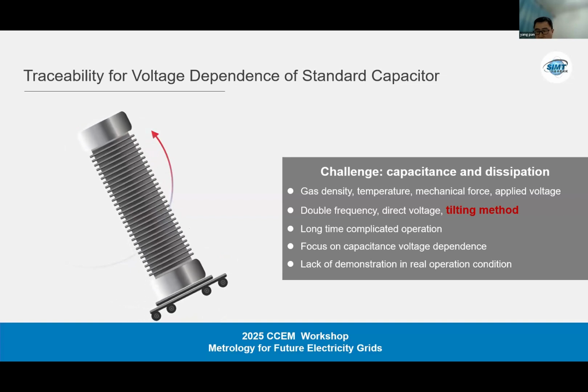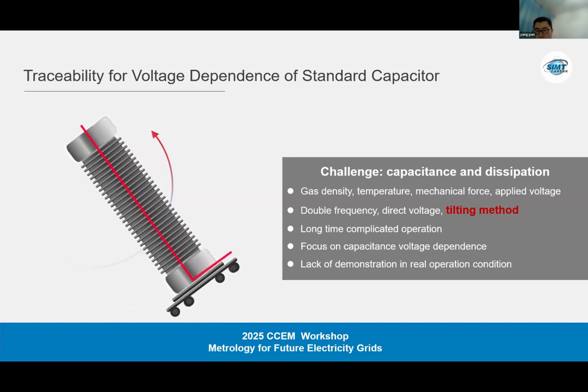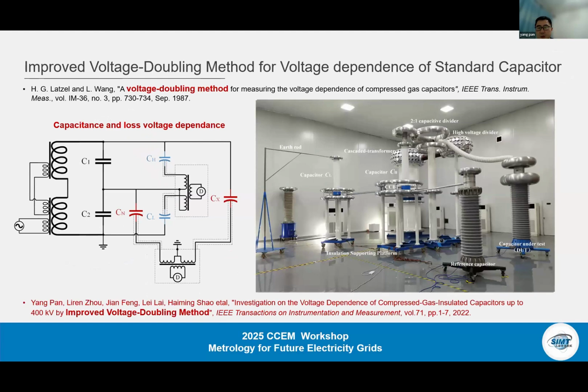Investigation has been carried out in this field, including the double frequency method, DC biasing method, tilting method, and also the voltage doubling method. Among all these test methods, the voltage doubling method offers a key advantage: the simultaneous determination of both the voltage coefficient of capacitance and the dissipation factor. Furthermore, the test is performed under actual power frequency operating conditions without requiring any specific preconditions. The voltage doubling method was initially proposed in 1987.